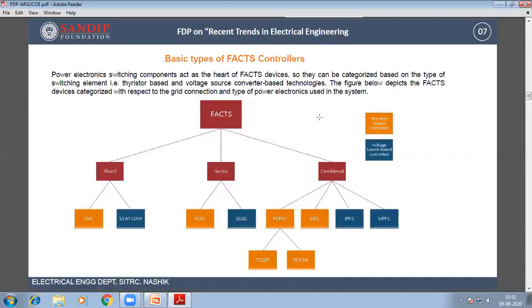But as far as transmission lines are concerned, both are not so efficient. That is why series compensation is widely used over long transmission lines. The third one is UPFC, or the hybrid controller, a combination of series and shunt controller, widely adopted over transmission lines. It can achieve control at the sending end, receiving end, and midpoint. So that is a fabulous one.